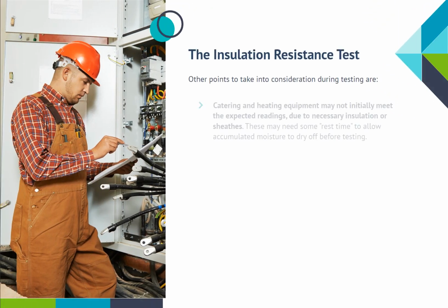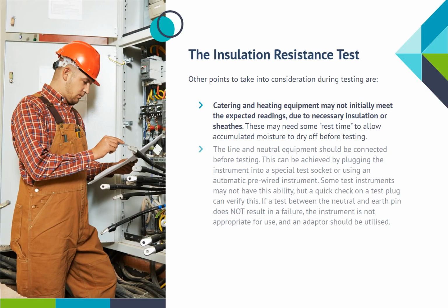Other points to take into consideration during testing are: catering and heating equipment may not initially meet the expected readings due to necessary insulation or sheaths. These may need some rest time to allow accumulated moisture to dry off before testing. The line and neutral equipment should be connected before testing. This can be achieved by plugging the instrument into a special test socket or using an automatic pre-wired instrument.